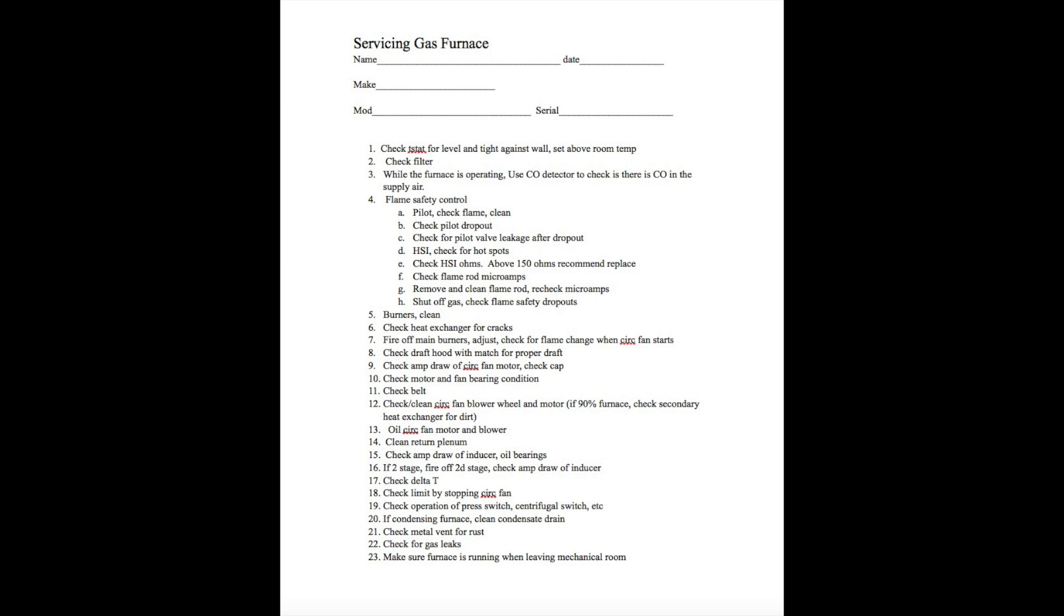The last thing, some of these furnaces you have turned the gas valve on and off. That valve may not have been turned on and off for years and years. Get your electronic gas leak detector and go over that thing and make sure there's no gas leaks. Your nose is your first indication, that's the best indication. But go over it with your electronic and make sure there are no gas leaks.